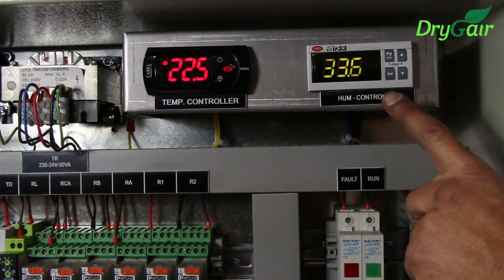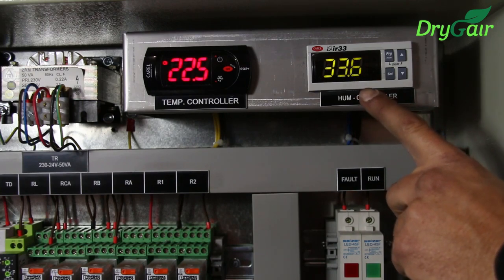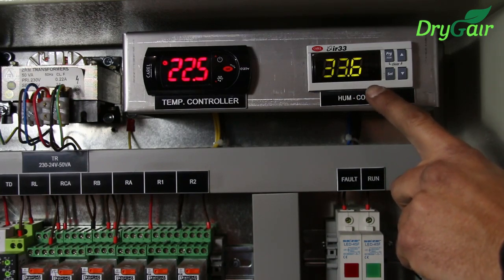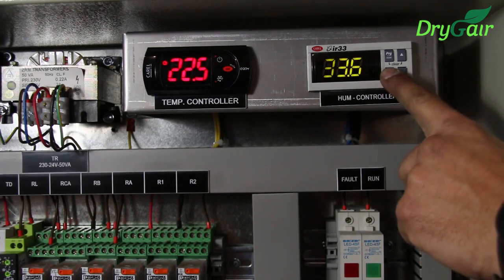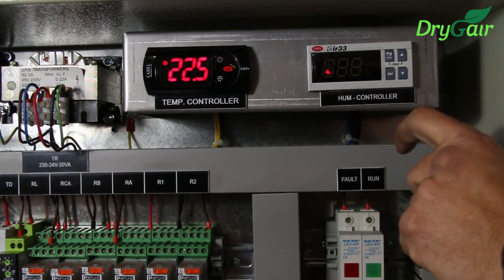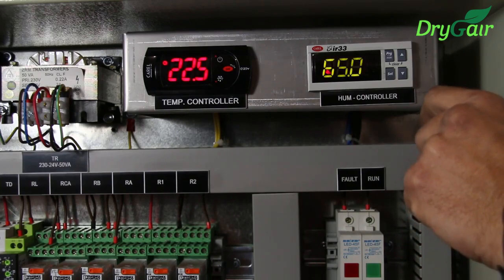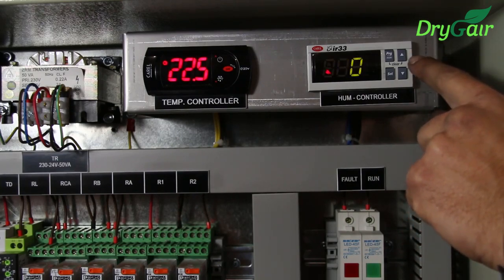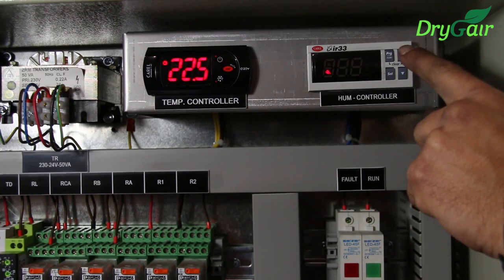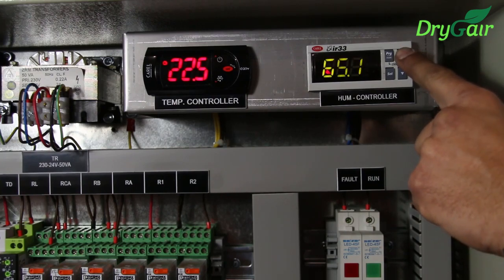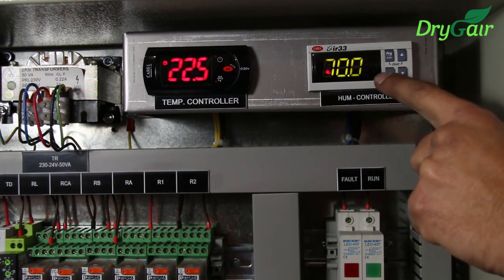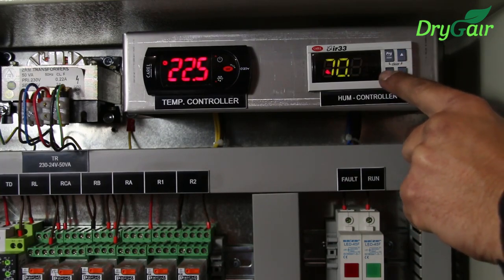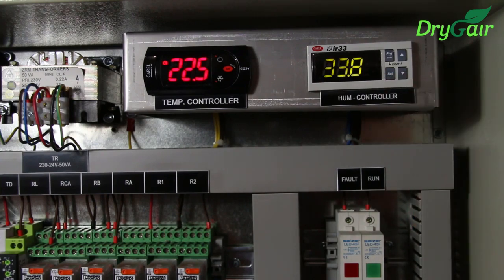To set the required humidity percentage, first press the Set button once, and the screen will display ST1. Once you release the Set button, the default humidity set point will flash on the display screen. Using the up and down arrow buttons, set the value to the required humidity percentage. Right now, the humidity set point Yair wants is 70%. Press the Set button again to save the change, and the current humidity level that the sensor reads will be displayed on the screen.